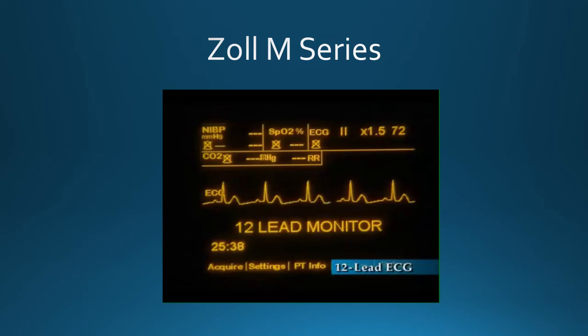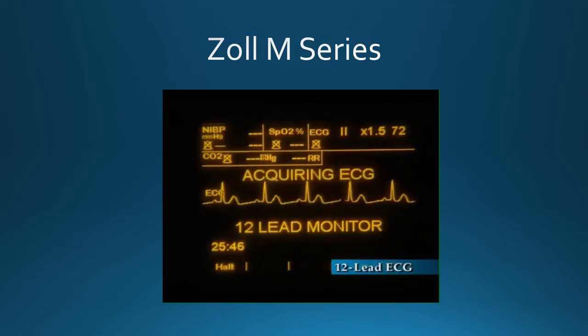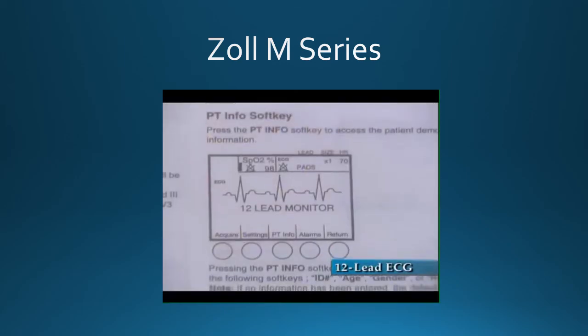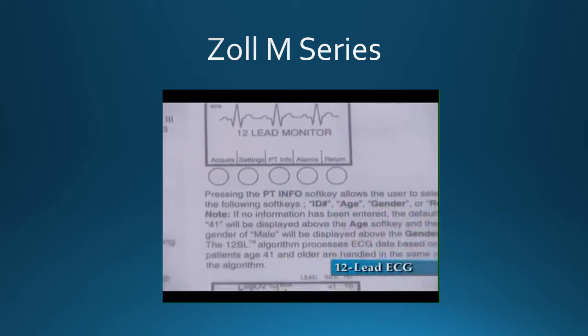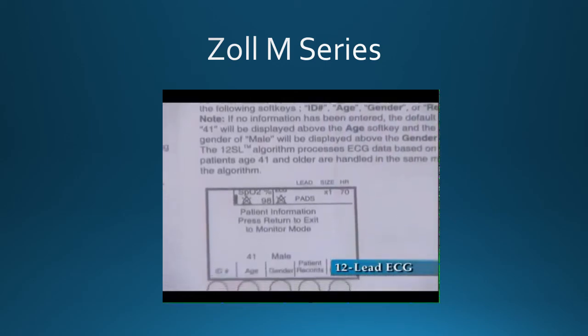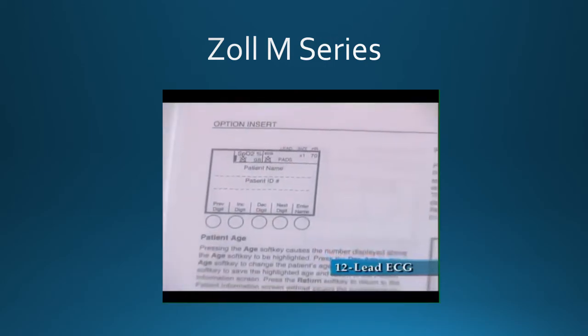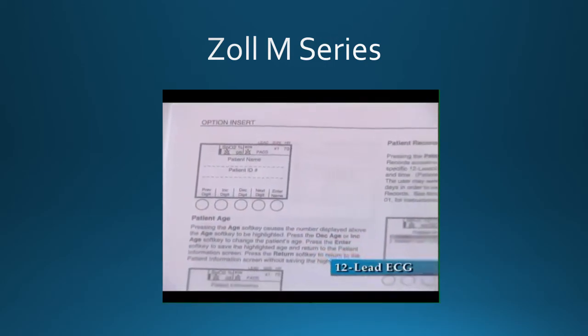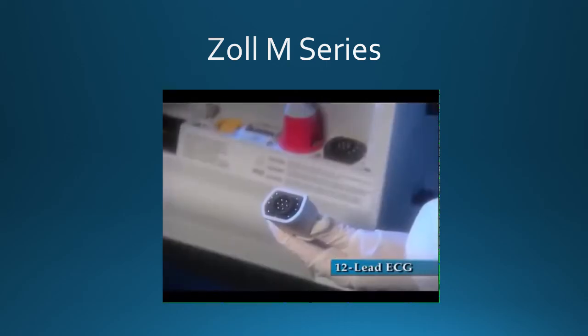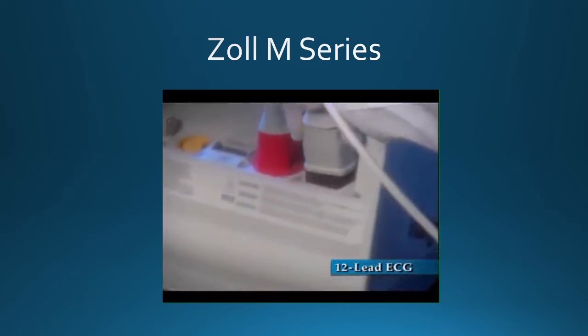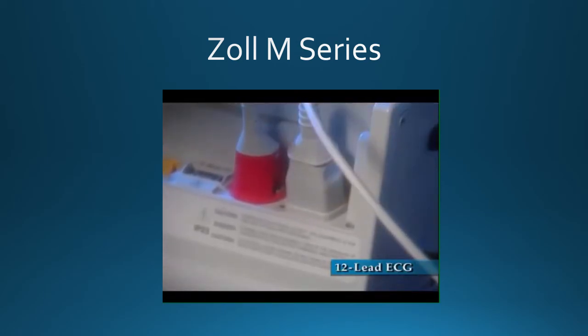M-Series defibrillators may be equipped with 12-lead ECG capabilities that provide simultaneous acquisition, storage, display, and ECG analysis using the GE Medical Systems 12SL program. Transmission to a fax machine or directly to GE Medical Systems Catalyst Muse is also available. Users should read the detailed instructions found in the M-Series 12-lead ECG Monitoring Operator's Guide. The M-Series Operator's Guide also gives detailed instructions on entering patient data. To acquire a 12-lead ECG, the one-step patient cable should be inserted into the ECG cable connector in the rear of the M-Series.